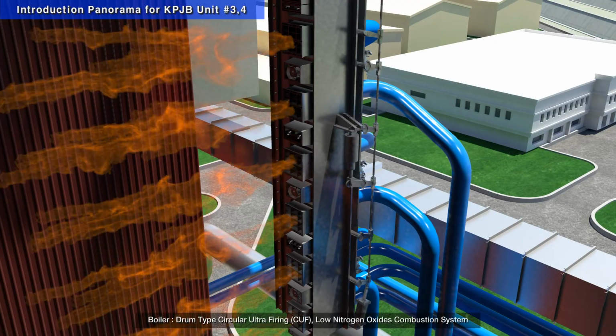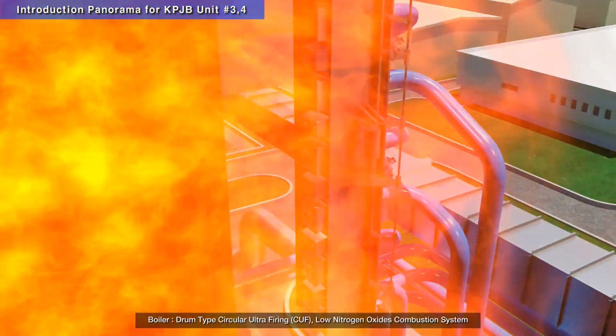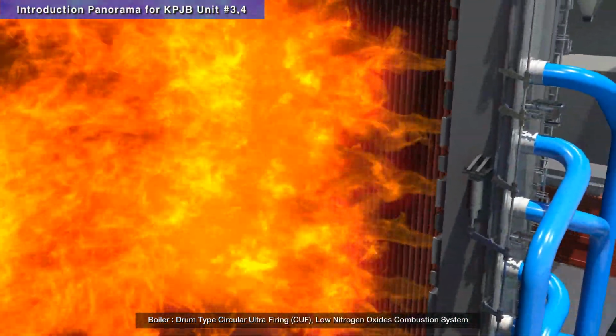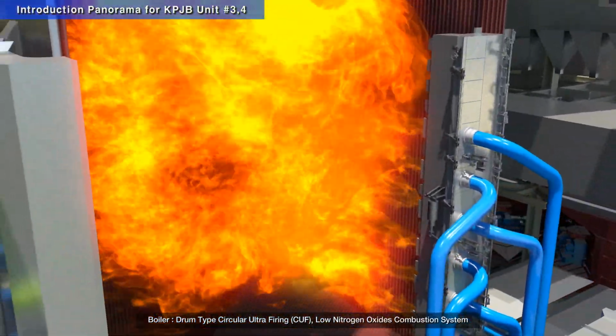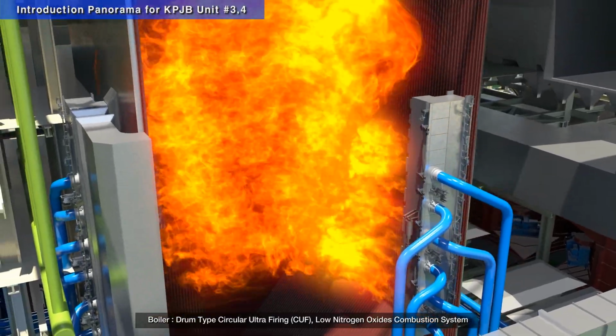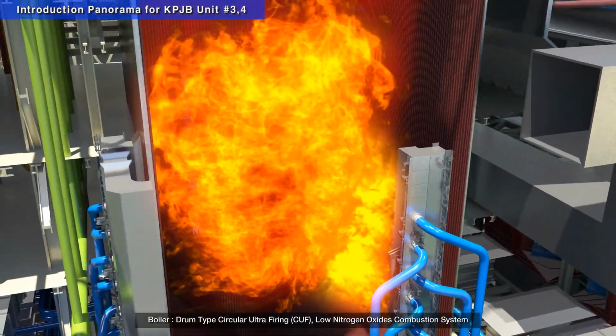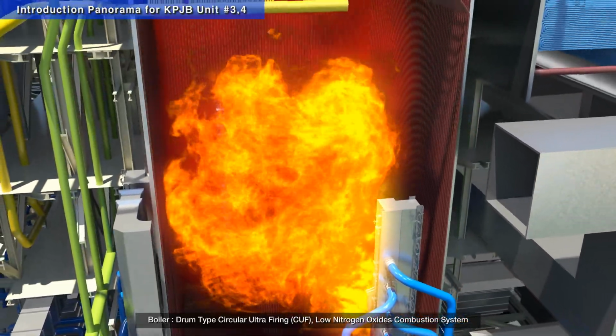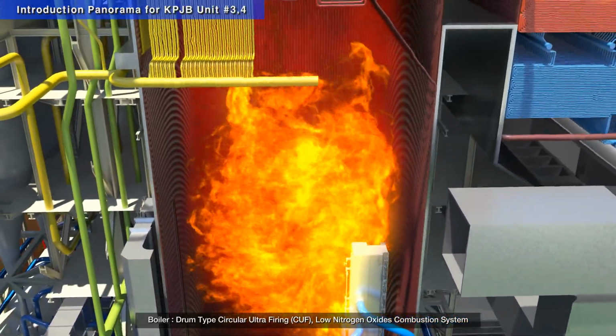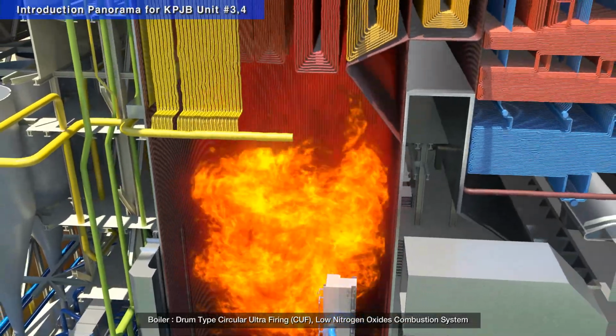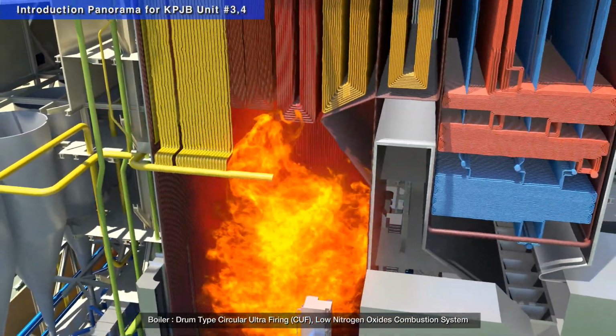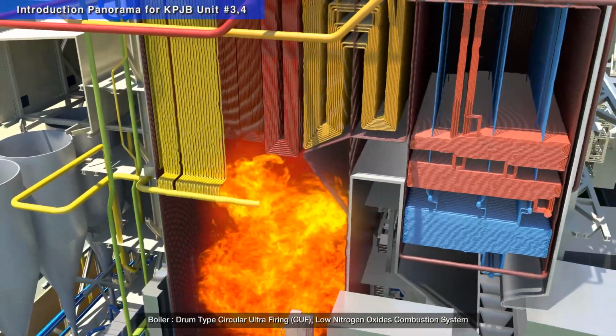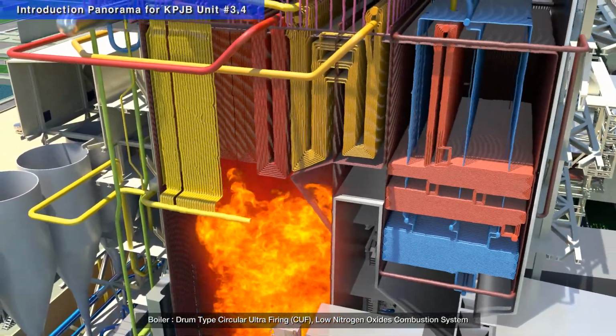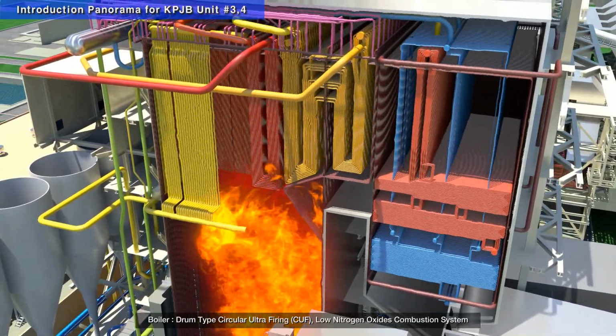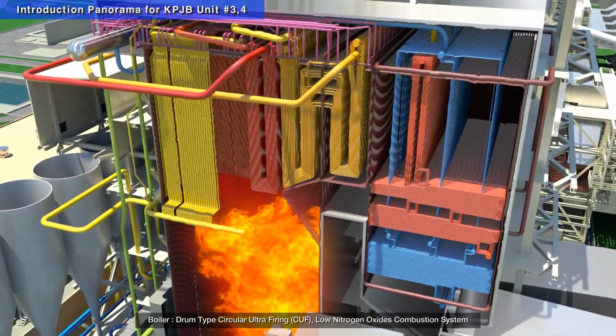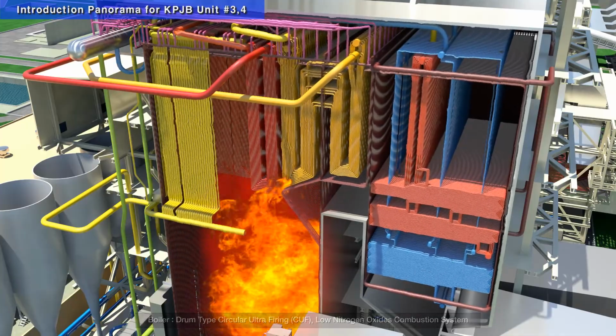KPJB Unit #3,4 power plant boiler is a drum-type circular ultra-firing, low nitrogen oxides combustion system which uses the variable pressure operation when in partial load with single-stage reheat, balanced draft, high-pressure turbine bypass system. This boiler produces 2,285.5 tons of steam per hour when in maximum continuous evaporation, 175.3 bar pressure, 541 degrees Celsius steam by burning coal of 278.5 tons per hour per unit.